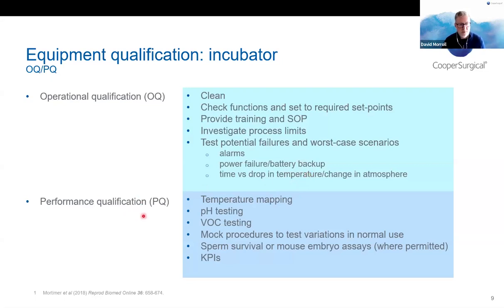And then in the performance qualification, that's around making sure we understand that everything's working as it should for conditions that mimic what we would be doing in the lab. So we'll look at temperature mapping, pH testing, VOC testing, and then doing mock procedures to test how that works in normal use. So for example, in a box incubator, you'd want to see the impact of repetitive openings of the door.